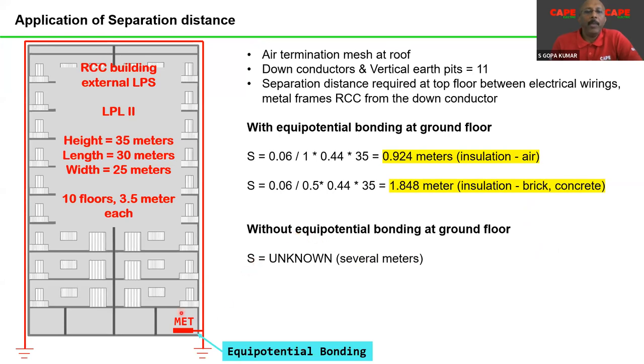And this is with the equipotential bonding at the bottom of the building. Now, if you don't have the equipotential bonding at the bottom of the building, the separation distance is really unknown. It may be several meters. Now, the question is, when you do lightning protection, are you making this equipotential bonding? You are making an exposed lightning protection system. Are you making the equipotential bonding?